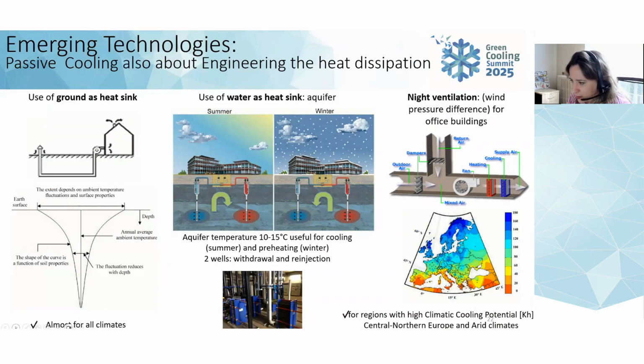In terms of engineering passive cooling, it's about heat dissipation, which can be done in the ground, in the water, or in the sky. Using the ground as a heat sink is possible in almost all climates: near the surface, ground and air temperatures are almost the same, but from a depth of 2 to 3 meters, the temperature approaches the annual average ambient temperature, which is below room comfort temperature in almost all climates. For this approach, adequate system design in terms of depth, diameters, length of pipes, and air velocities is required.